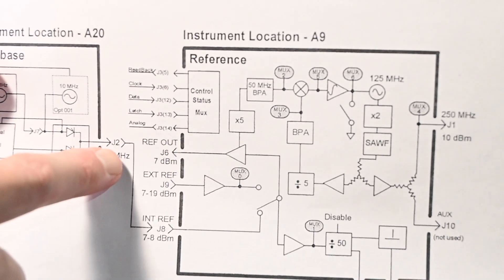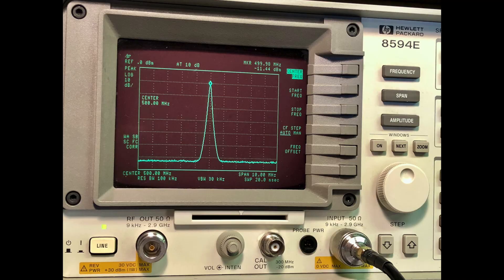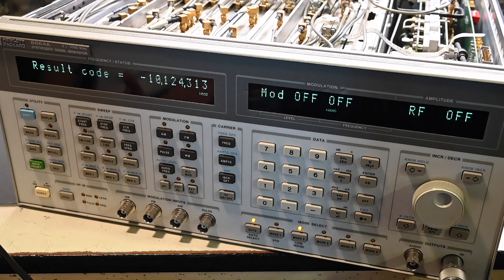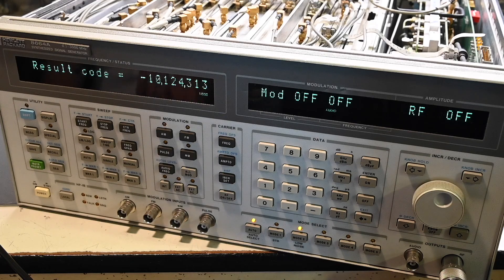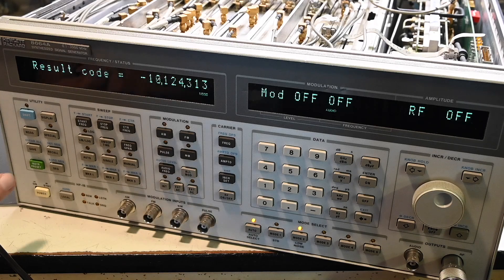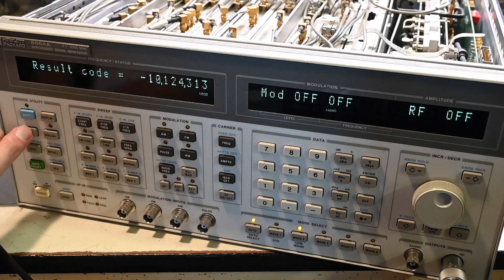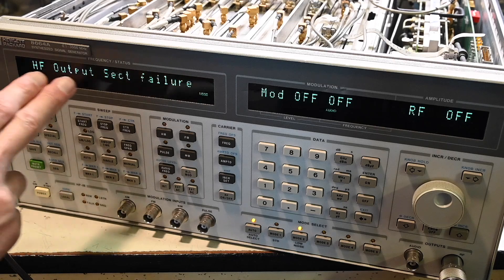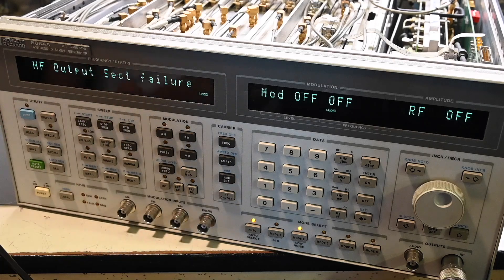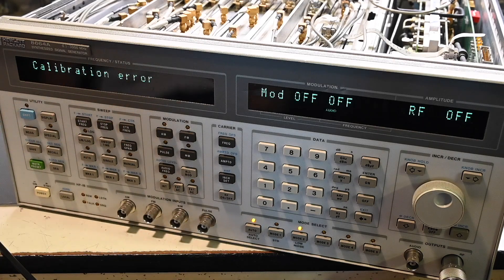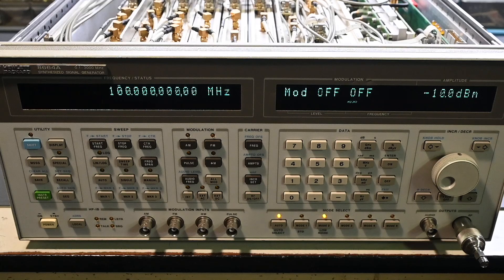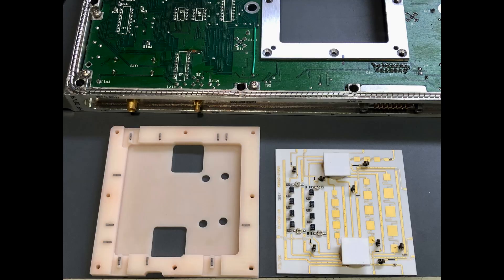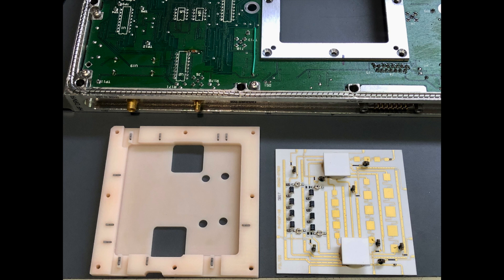Although the main output signal looked okay at first, as we saw in part two, I started to notice some instability and the HF driver module failed its self-test. Also, two fault indicators were turning on at certain frequencies, and the HF driver module did not calibrate correctly, so there were definitely some issues going on. The problem was traced to poor connections on the very small conductive foam pads linking the hybrid modules to the circuit board inside the HF driver module.